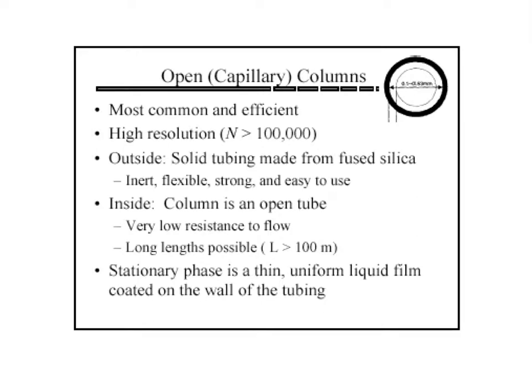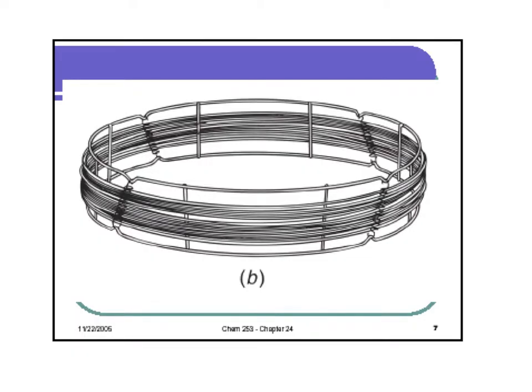A capillary column consists of a thin film of the liquid phase coated onto the inside wall of a very small diameter glass tube. Here you see the cross-section of a capillary column. This column is more like a straw, and the components of the mixture contact the liquid phase on the walls as the gas moves through the center of the column. These columns are typically very long and have many more theoretical plates, greater than 100,000. Columns of this length must be wound many times in order to fit into the instrument. The metal support keeps the thin glass of the column from being crushed or broken.